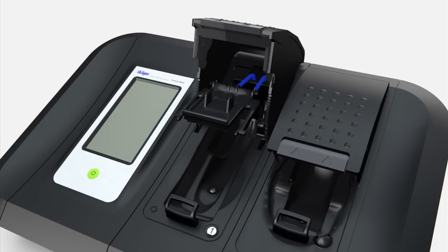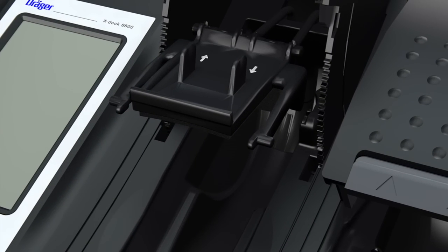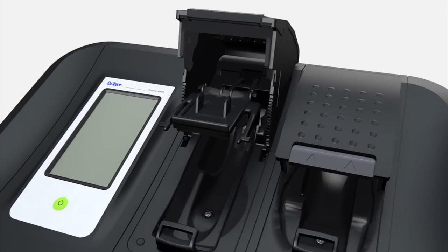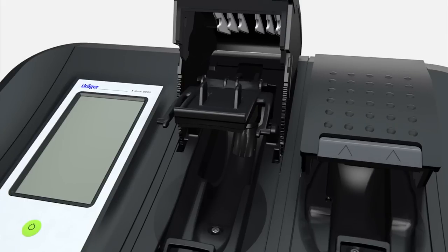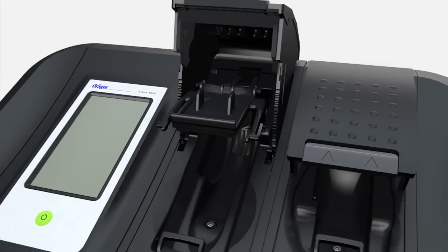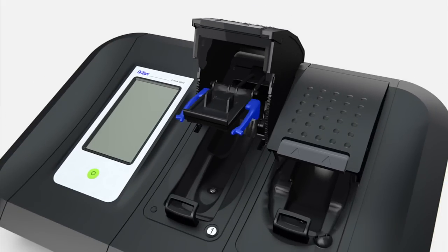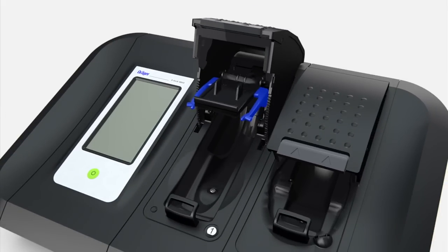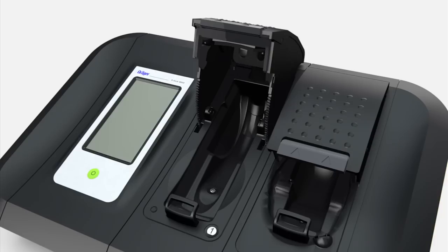Attach the tubes to the new sealing insert. Make sure that the hinge and joint interlock. Push the outer lugs inwards and insert the sealing insert into the module lid until the locking lugs click into place.